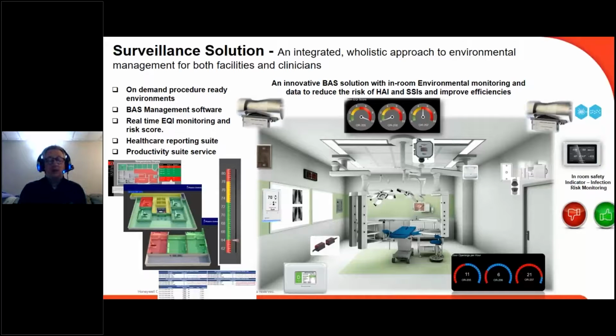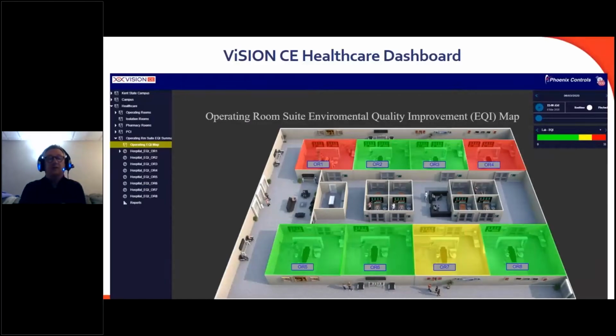And so we do that with environmental parameters, like I said. We monitor temperature, humidity, door switches, right, for activity, VOCs, velocities in the duct, particle counts, pressure. All those contribute to the environment quality, which also contributes to the infection risk. And basically, taking all that information along with the consultant's consultation, they have an algorithm that correlates all that into a microbial load, providing that hospital with the risk picture, right? And it's pretty easily visually done with a dashboard.